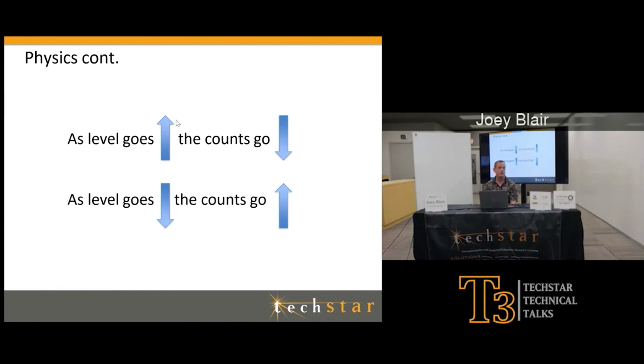Well, that's normal, right? If you think about it, I've come under pressure and I'm starting to compress some of that vapor inside of it, so it's getting a little thicker in there, so it's blocking a little more radiation. So now I'm at 10,000 counts. At that point, I would go in and hook up to my detector and take a reading. So for that 10,000, I say take counts, and it's going to say 10,000. Then I'm going to tell it, what does that 10,000 equal? And I'll write inside my software that it equals 0% level. The detector's like, cool, I know where my zero is. It's 10,000 counts. Then I start filling up my process.